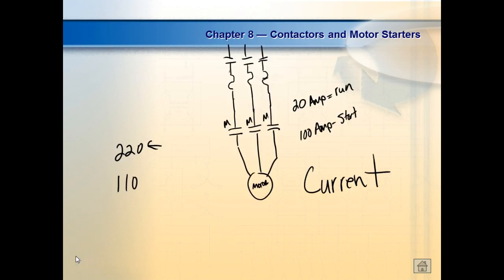So what we're saying is that if I've got a single voltage motor, there's a high probability that the overloads are built inside, and it'll be on the nameplate. So if you ever get a motor and it says thermally protected, what does that mean? It means it's got internal overloads. And some of them have reset buttons on the outside too. The little thermal overloads are dangerous because once they cool back off, the motor will kick back in. Just about every motor in your house has those little internal thermal overloads.